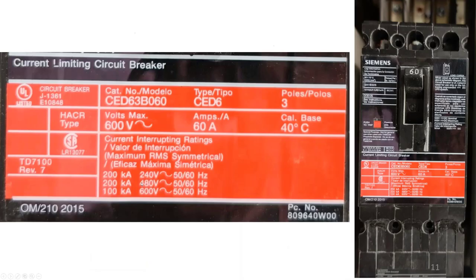Also, you have to consider another thing. Circuit breakers are available today as high as 200 kAIC. And I'm surprised that not a lot of people know about these. So you can buy a circuit breaker, this is just a standard 60-amp circuit breaker, and it can go up to 200,000 AIC. Yes, smoke will come out of it when it trips, but it will trip. And in some cases, this is the solution rather than putting fuses.